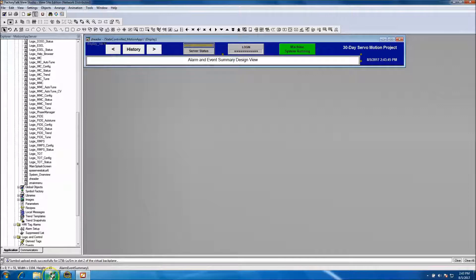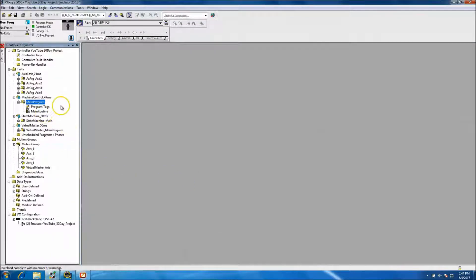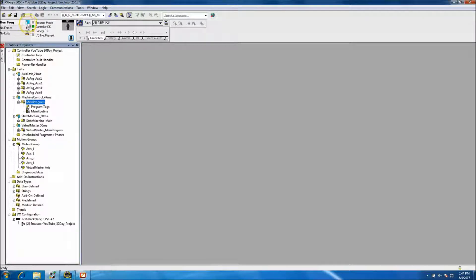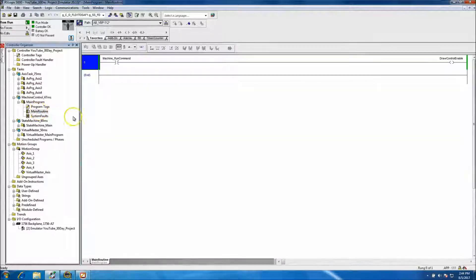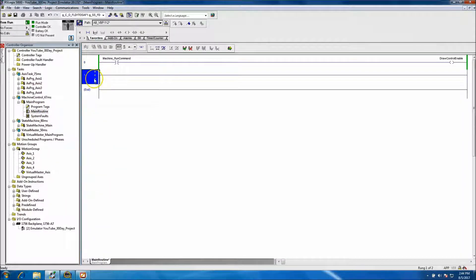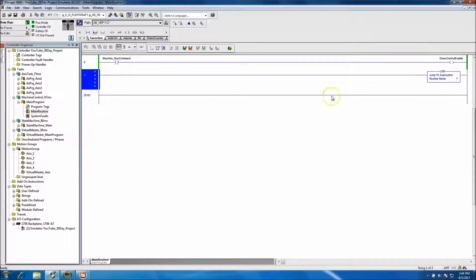We use an ALMD instruction in the ControlLogix platform. In the ACD file, we'll come into the main control, which is the main routine, and we're going to add a fault routine — we'll just call it 'System Faults.' Now we have System Faults. We'll come back up into our main routine, add a rung, and add a JSR to jump to subroutine for the routine we added. Now that's done and it's live.